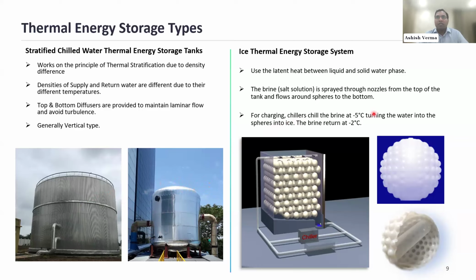Another form is the ice-based thermal energy storage tank, where there are plastic balls with a material inside, mostly water or a salt solution. The water, or the brine or salt solution, is sprayed over these balls, where inside the ball there is water. The water freezes and stores energy in the form of latent heat. Whenever we need cooling from the thermal energy storage, this ice starts melting and provides cooling for the requirement.